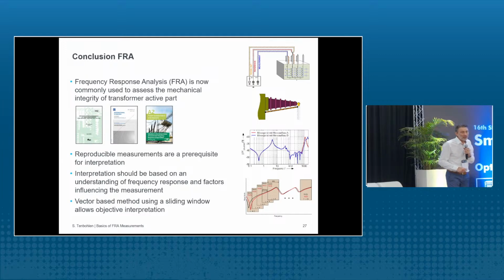Okay, so let's conclude with the FRA. In the beginning it was a quite academic diagnostic technique, but now it's already standardized. We have an IEC standard which describes how to perform an FRA measurement. Normally during the factory acceptance test, such an FRA is measured, since the last 5 to 6 years. But for the interpretation of the FRA, this standard up to now does not give any recommendations, and so Cigre worked out and gave proposals like I presented here. So in future we can have an objective interpretation, and they also now start to revise the standard, and in the next revision of the standard these rules will be implemented.